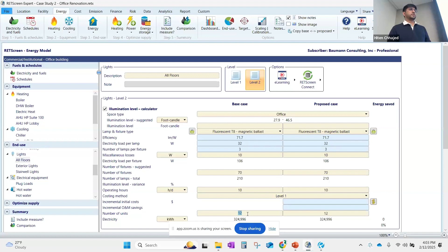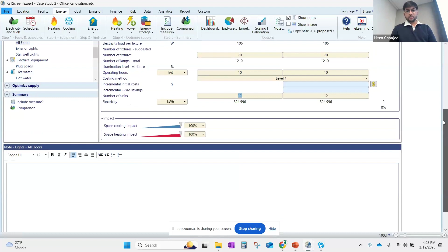So similar to what we have in this room, I can see that there are 2 lamps. We have 3 lamps for each fixture. These fluorescent T8s, because they are so old, also have some miscellaneous losses. Losses are assumed to be 10 watts. There are 70 fixtures on a single floor, and there are a total of 12 floors in the building. And that gives you around 324,000 kilowatt hour for just the floor lighting.